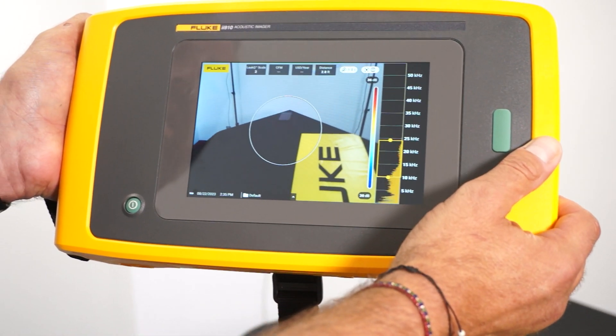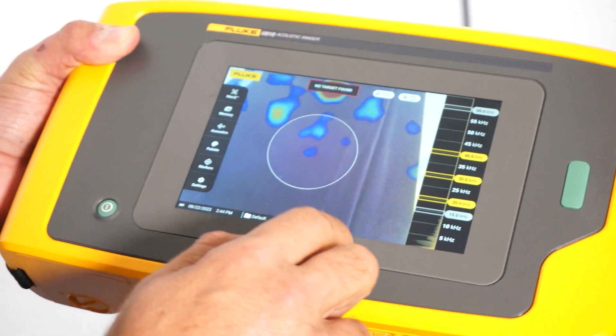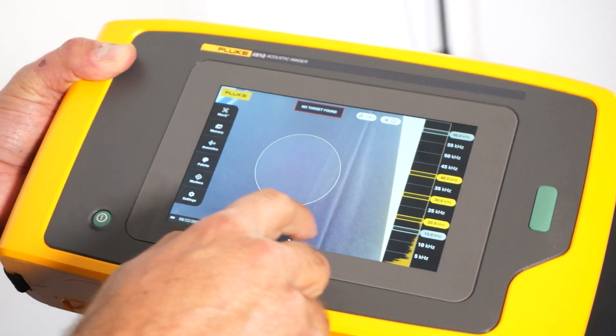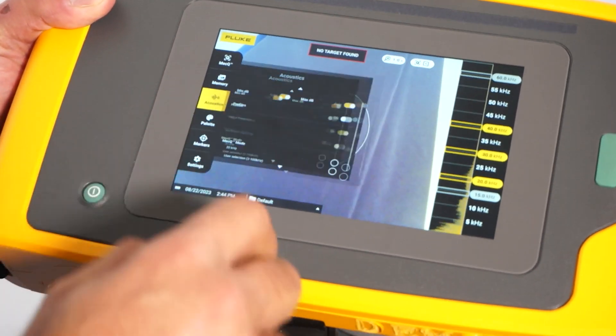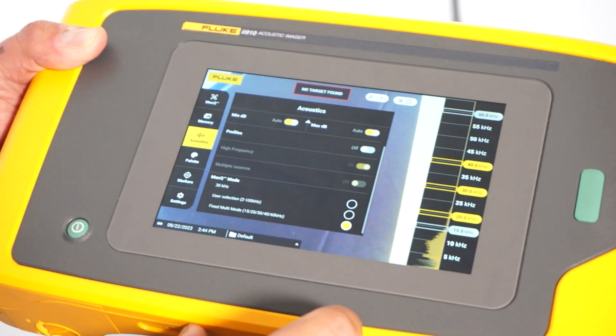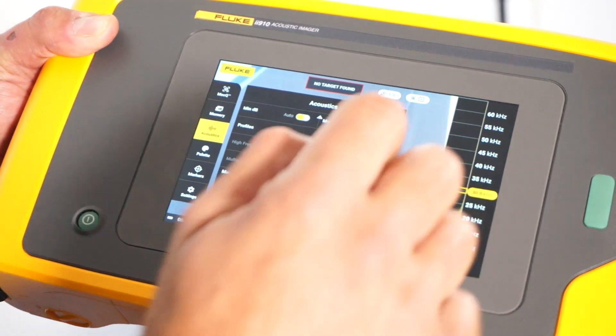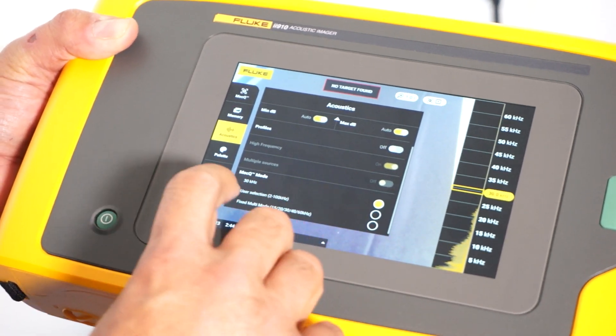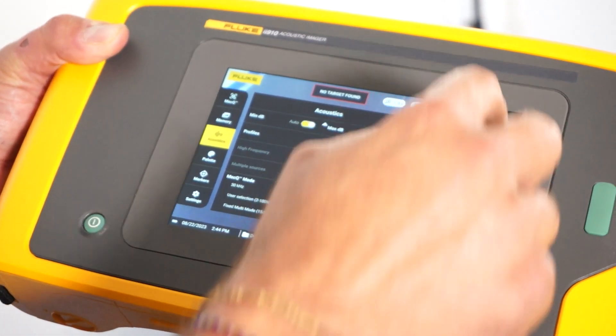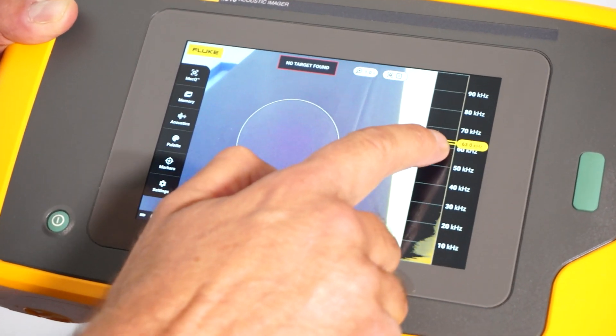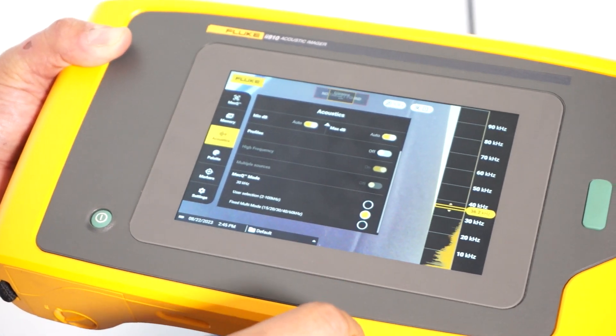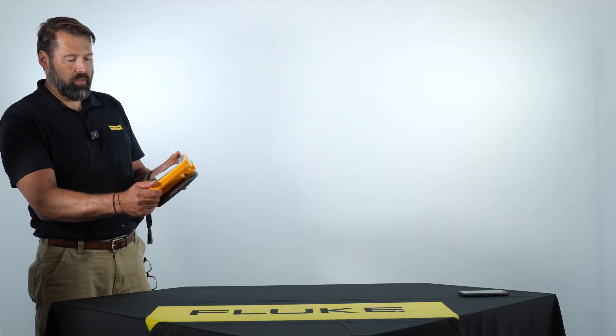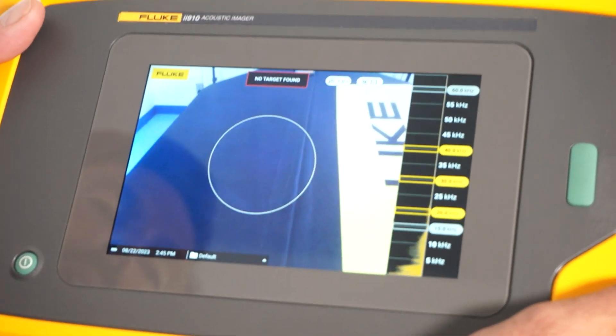That is a quick overview of some of the new features of the LeakQ Mode. Now we're going to take a look at the MechQ Mode. Once you're in MechQ Mode, you've got a few different options. Under Acoustics, scrolling to the bottom, there are three different settings: the first is a fixed 30 kilohertz range, the second is user-selected from 2 up to 100 kilohertz with a slider to adjust, and the third is a fixed multi-mode giving fixed frequency ranges at 20, 30, and 40 kilohertz.